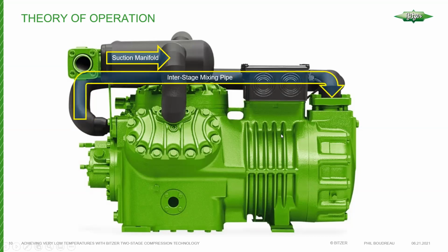Next, we have the interstage mixing pipe. This interstage mixing pipe is actually at interstage pressure. That's that 61 PSI or so in the case of a -50 and 100 system. And in this case, the refrigerant that leaves those 4 low stage cylinders now is sent to the back of the compressor where the motor barrel is, because this is a refrigerant cooled motor.